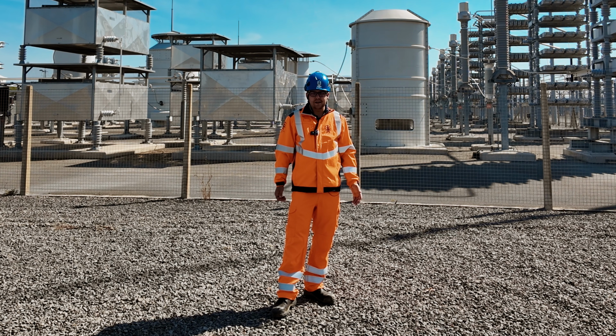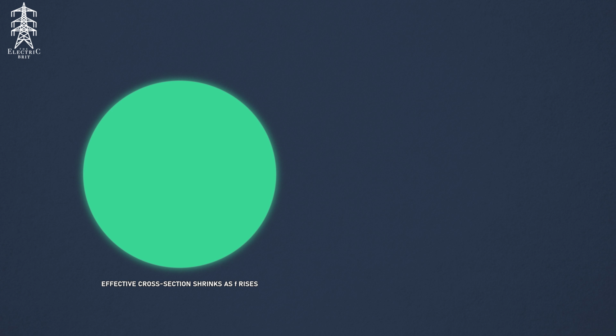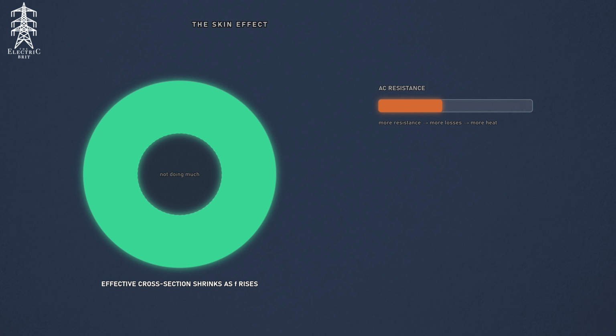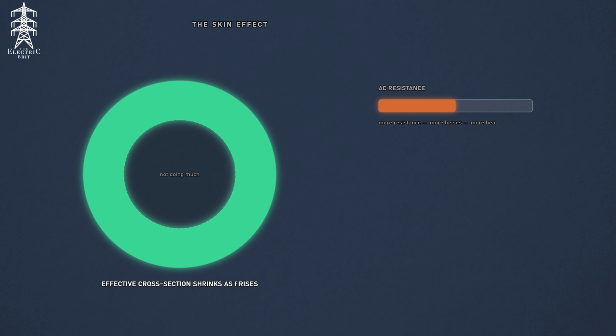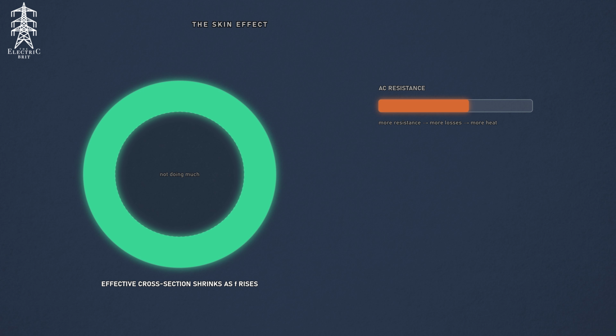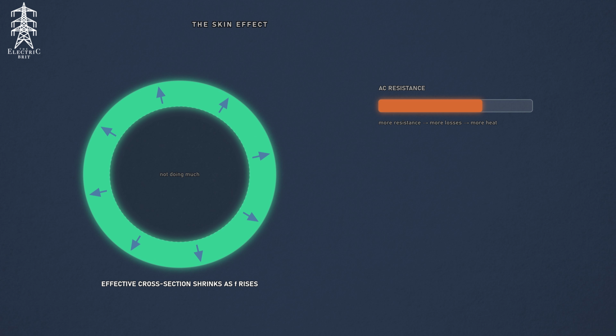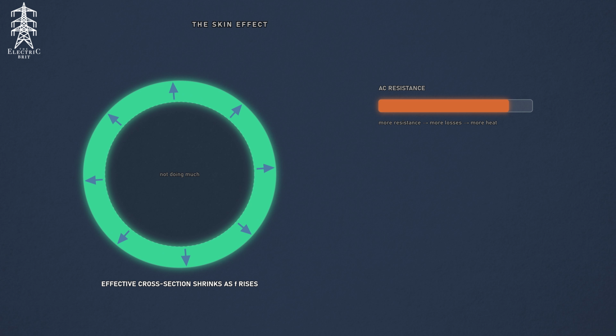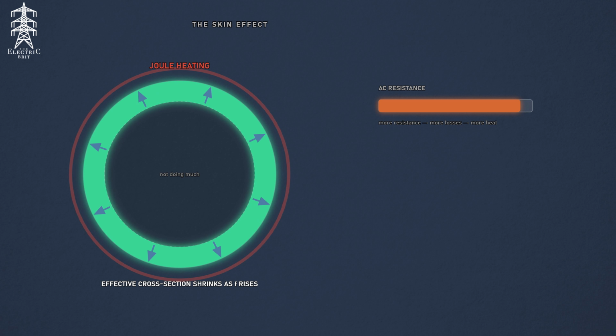So why are harmonics generating heat? That goes back to our dear friend the skin effect, which I also explained in that video. Essentially, as frequency increases, current becomes increasingly concentrated towards the outside of the conductor, reducing its effective cross-sectional area and increasing its AC resistance. More resistance means more losses and more heat. At higher frequencies, the current alternates faster, creating a stronger opposing force inside the conductor, pushing more current towards the outside.